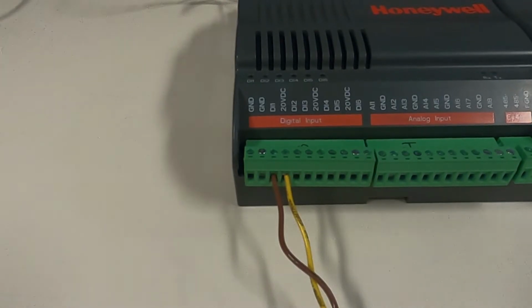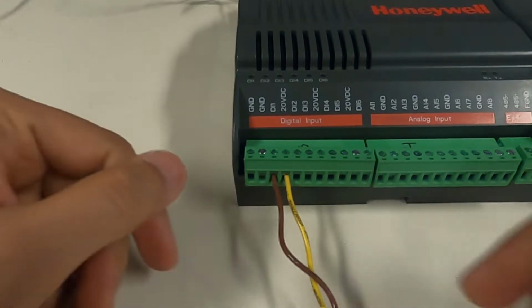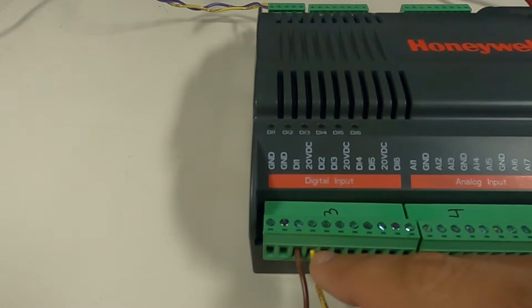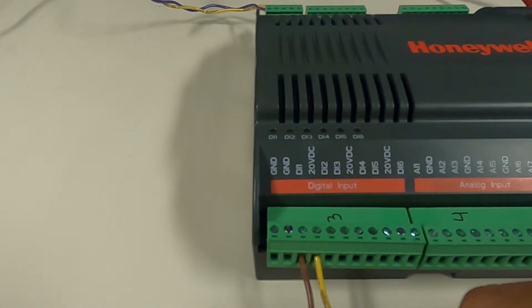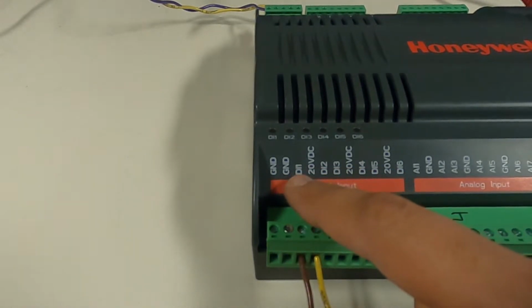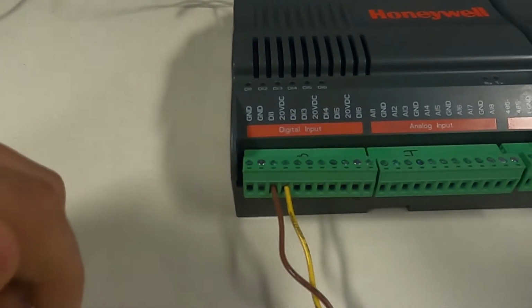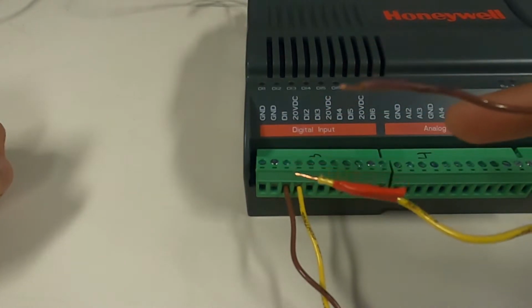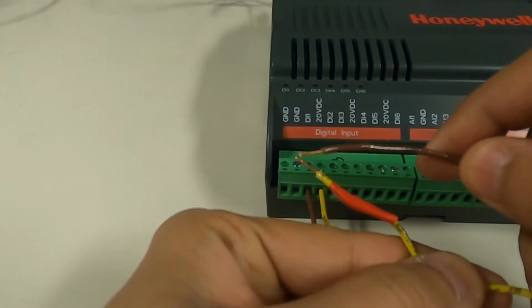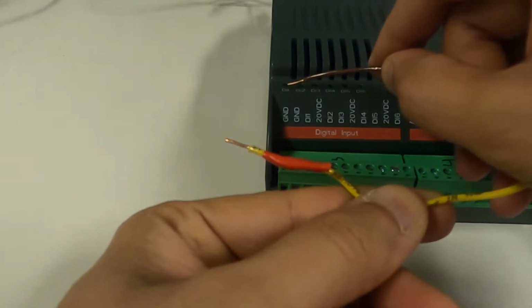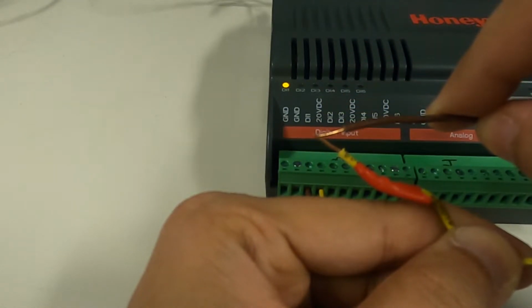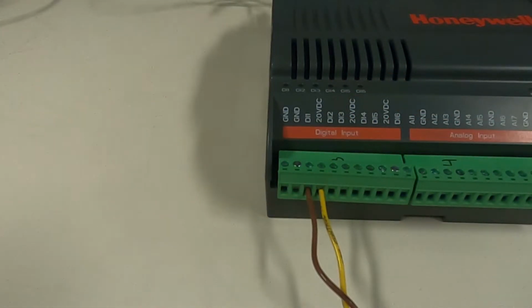Let's see with a physical device how you usually get a binary input to your DDC. Let us see that illustration physically on the field. For the binary input, as you can see, there is one single wire coming from 20-volt DC going out and another wire coming back as a digital input or binary input here. What I have is the other two ends of those two wires open here. As you can see, if I connect these two, you can see a light blinking right here, which says, hey, the circuit is closed. This is open. The circuit is closed. This is open. So that's what binary inputs is all about.